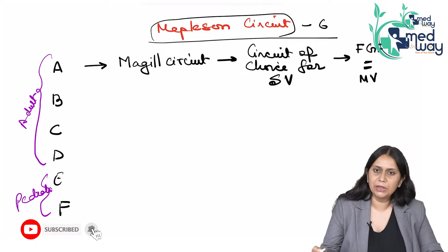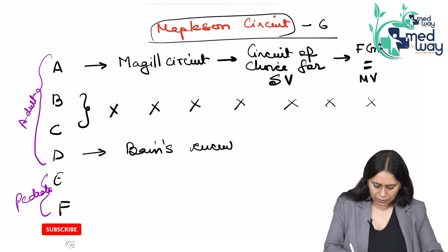This is Mapleson A. B and C we are not using, so they are not in clinical use, we don't have to remember them. Mapleson D, this is also called Bain's circuit, and this is the circuit of choice for controlled ventilation, for IPPV, and we keep the fresh gas flow at 1.8 times minute ventilation. So these 4 points we need to remember for adult.